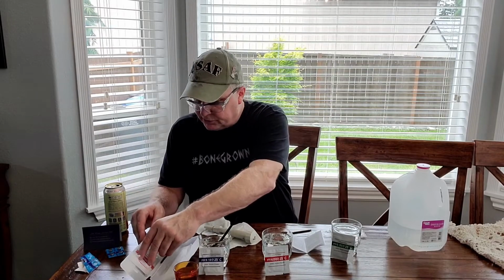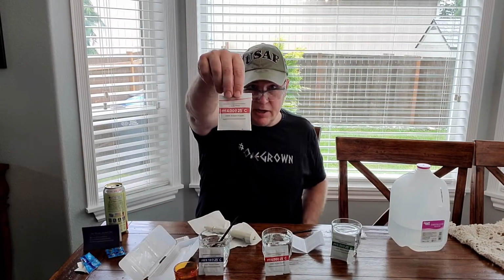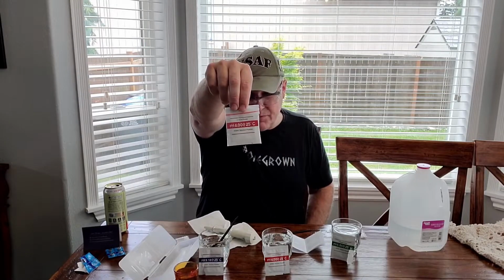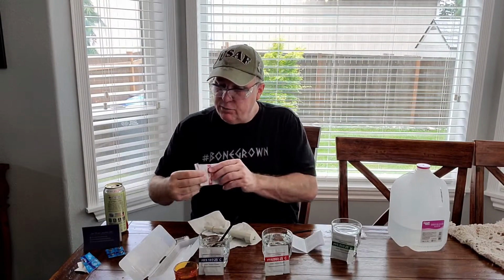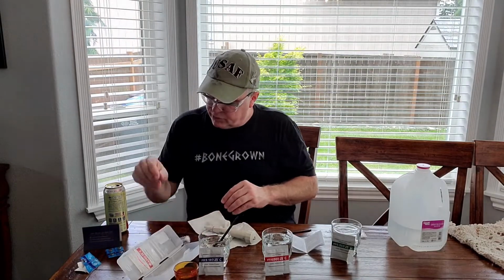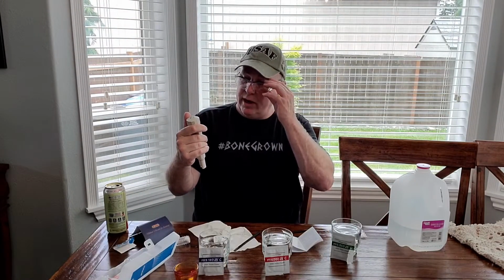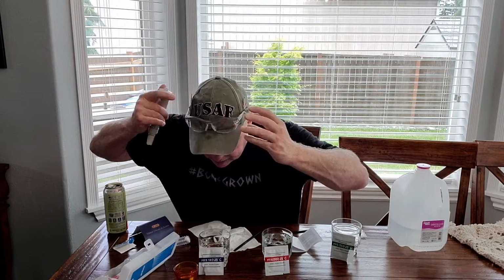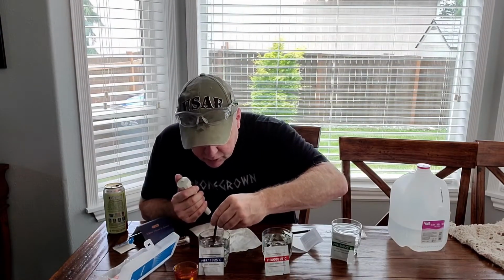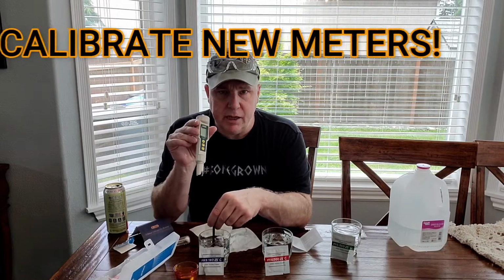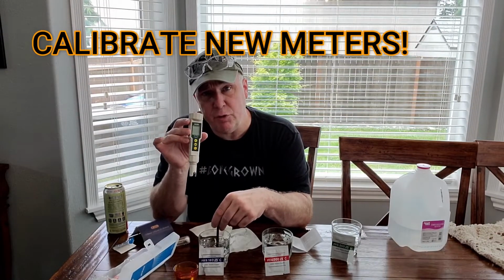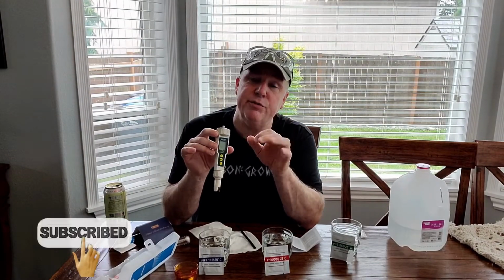While I'm stirring, I will say that this kit came with a second calibration set, so if you do have a problem, you think things are really out of whack, you can retest it again, and you can buy these online, folks. I went ahead now and I've got my solution. Let's double check it. A couple of little pieces still, so I want to stir it. But you should always do this, folks. When you get a new pH meter, always calibrate it. Make sure that this is right before you start, or it could be off a whole percent. And it highly recommends when you first get your pH meter to calibrate it.